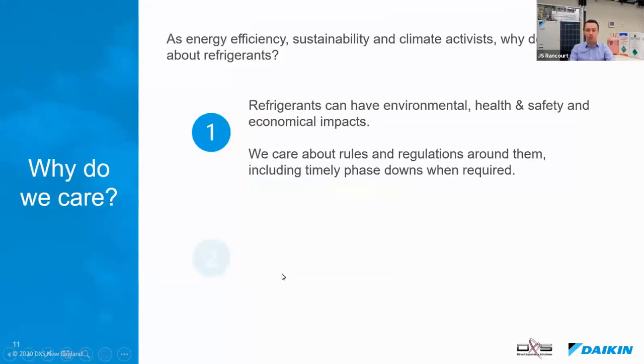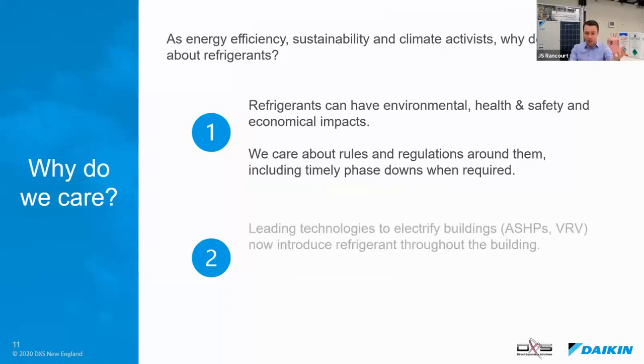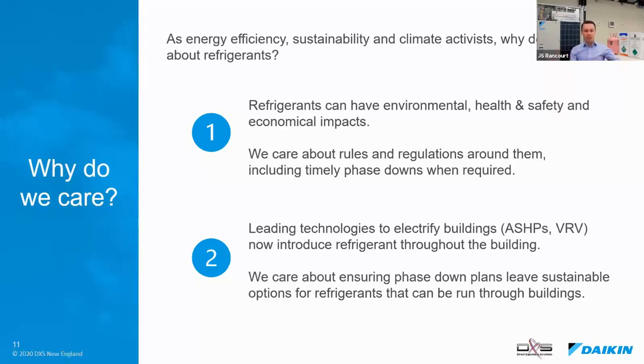So our second reason, and most important reason for us on this phone call as to why we care about refrigerants, is the leading technologies today to electrify buildings. It's not the only technologies, but still the leading technologies, air source heat pumps and VRV, now introduce refrigerants into the building. Instead of being outside in the air conditioner, on the roof, in a chiller, we're now distributing this through the building to get the heat into the building. Therefore, we care about ensuring that any phase downs leave sustainable options for refrigerants that can be run through buildings. And that's what we'll go through today.